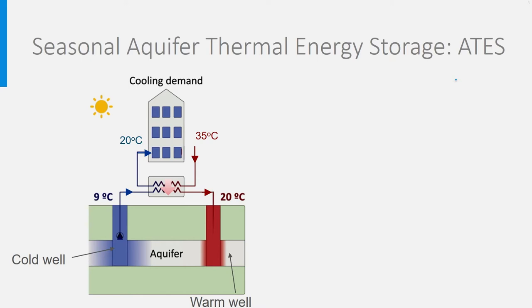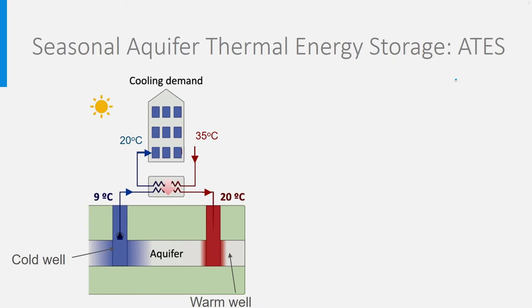So, the cold water from the aquifer is pumped and heated by the warm air up to 20 degrees in this example. This aquifer water at 20 degrees is then re-injected into the aquifer using a well placed far enough from the cold well, generally a few hundred meters.